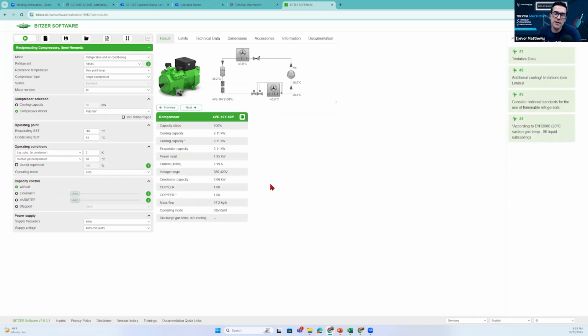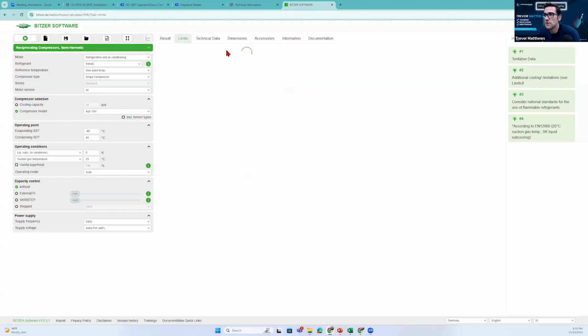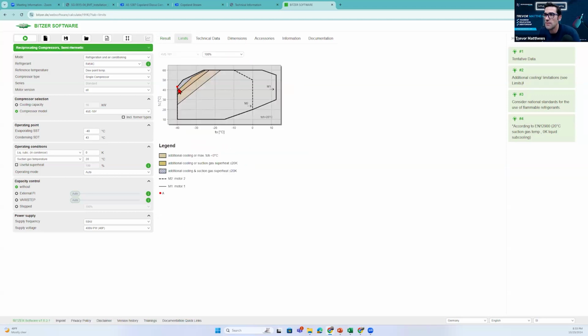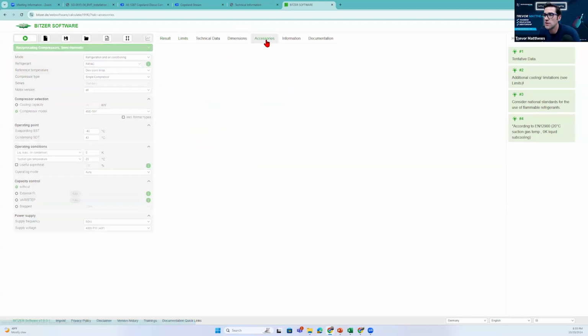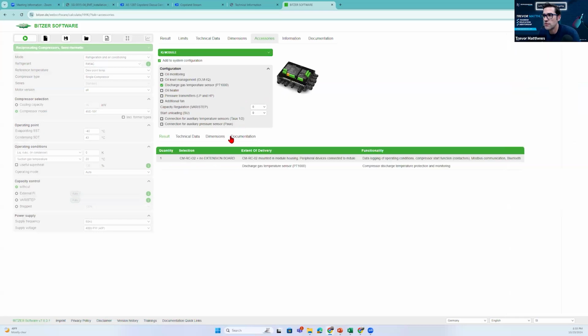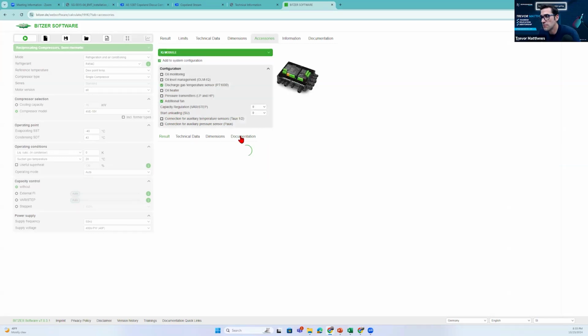You're like, well, why do I even care about this stuff? If you start to put this information in on all the systems you're working on and servicing, you can really get an understanding of exactly what's happening inside that compressor. Let's go to the limits. The same thing will be happening way up here. This one for sure should have liquid injection or refrigerant injection as an option. And it definitely doesn't. It just has additional fans on this one as well. That's impressive.